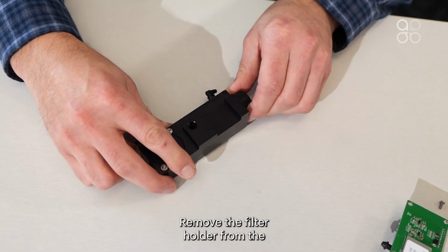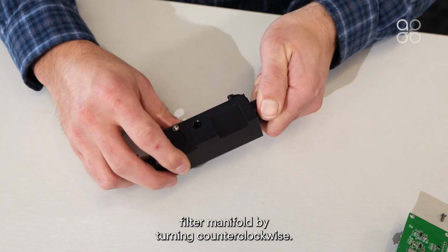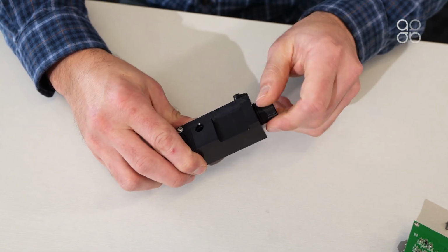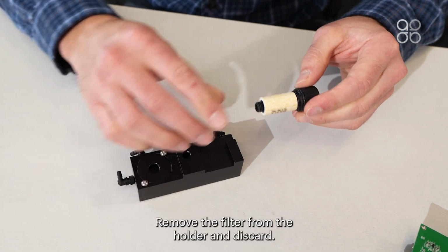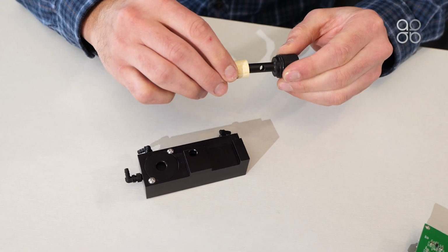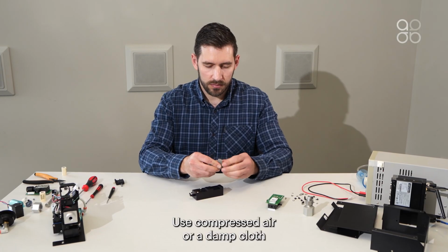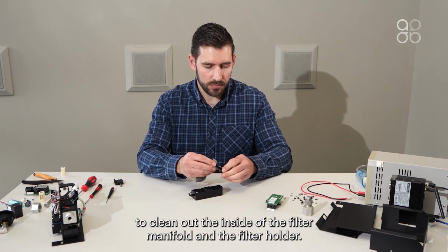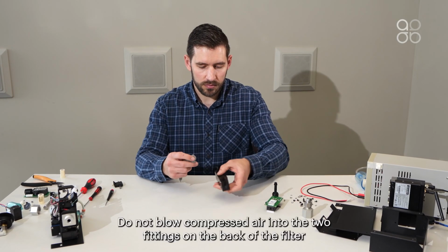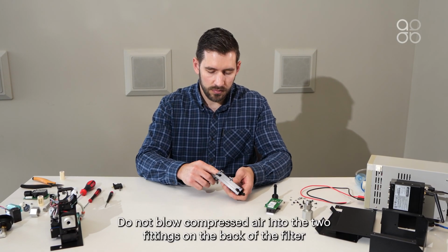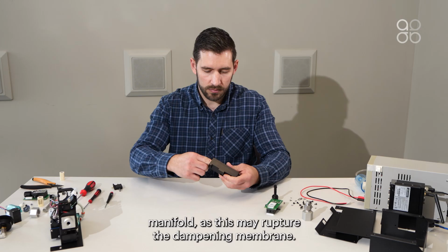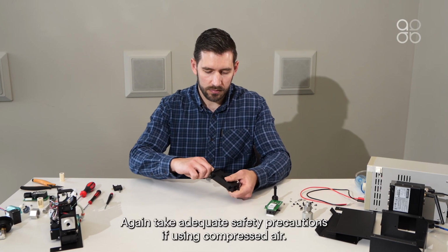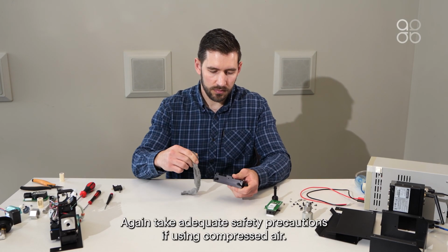Remove the filter holder from the filter manifold by turning counterclockwise. Remove the filter from the holder and discard. Use compressed air or a damp cloth to clean out the inside of the filter manifold and the filter holder. Do not blow compressed air into the 2 fittings on the back of the filter manifold, as this may rupture the dampening membrane. Again, take adequate safety precautions if using compressed air.